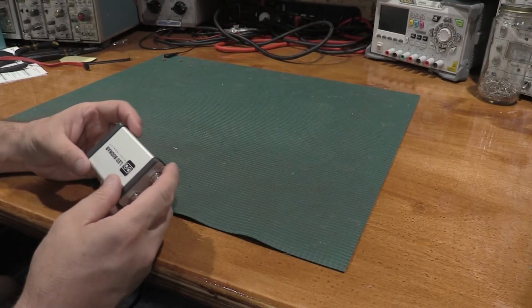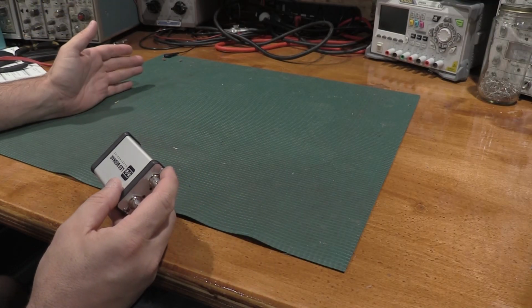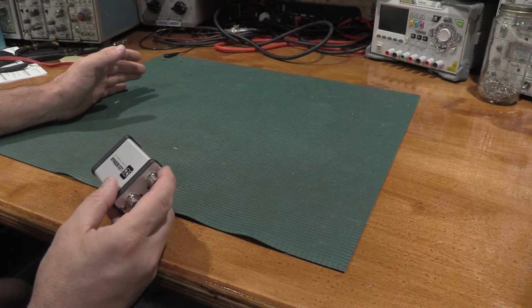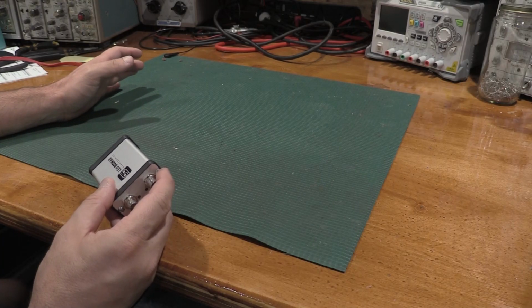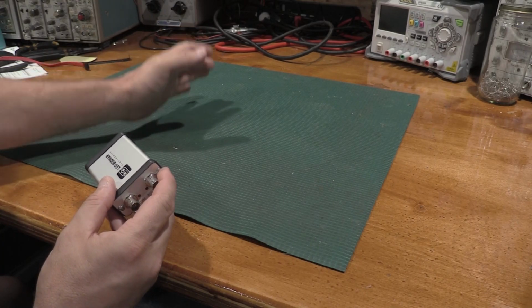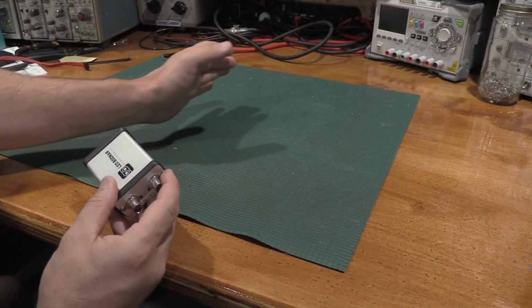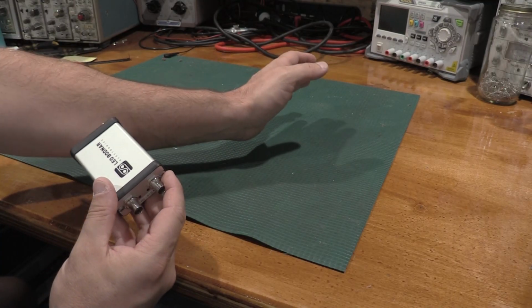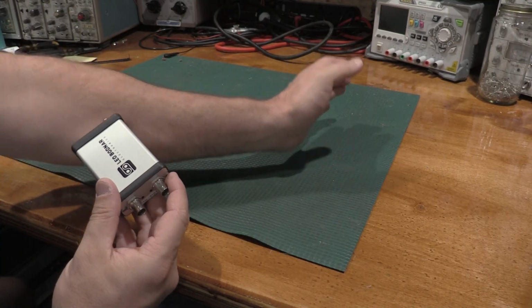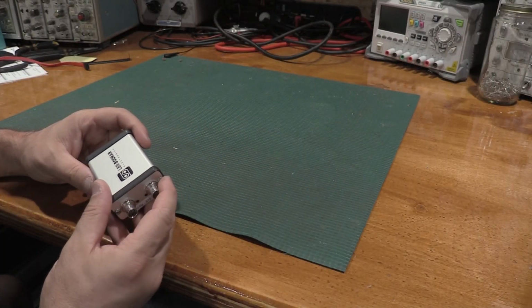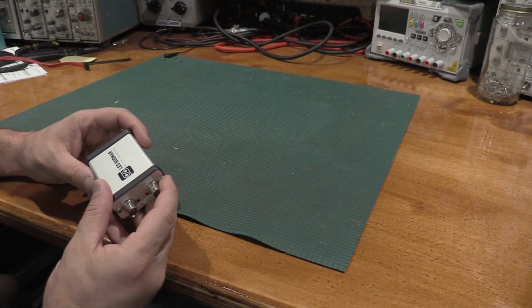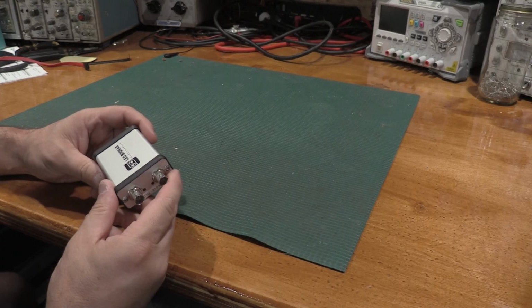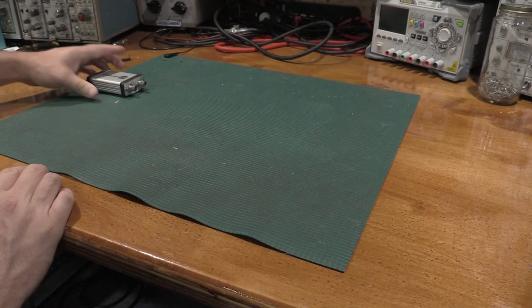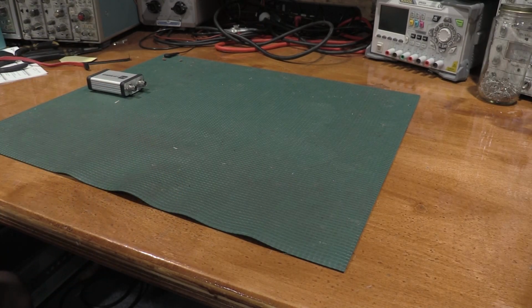So we're at rubidium. GPS comes in, and usually I see about 15 satellites where I'm at, so we get a really stable GPS signal. It goes into the GPSDO. The GPSDO does one pulse per second into the Stanford, and the Stanford takes over and does short-term stability for the measurements in the lab. Testing methodology on this is all this testing is done with a Keysight 53230A.